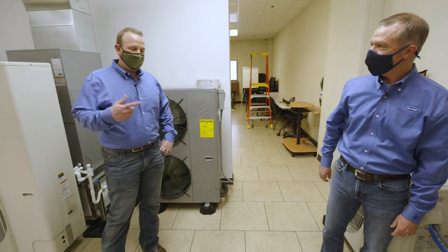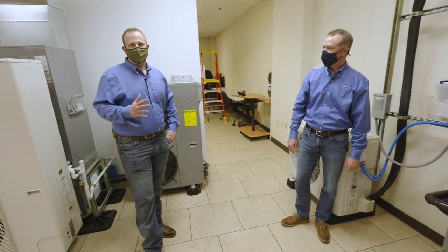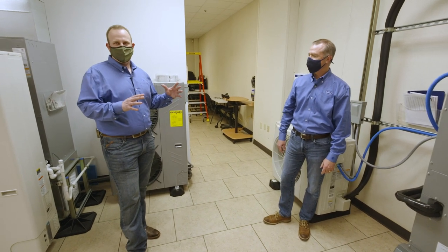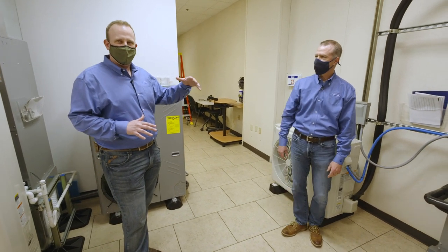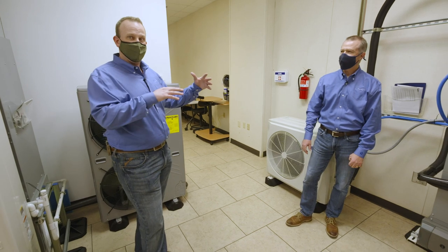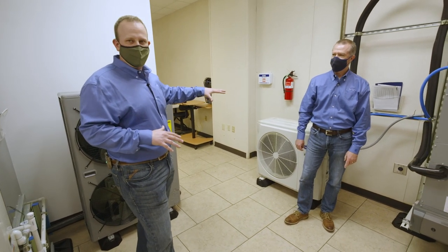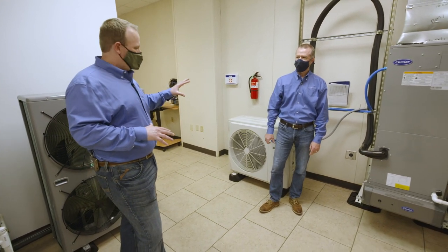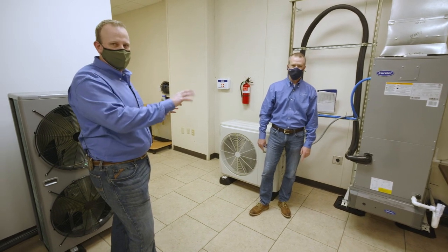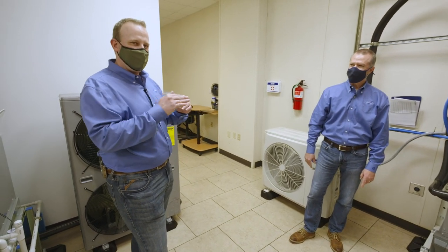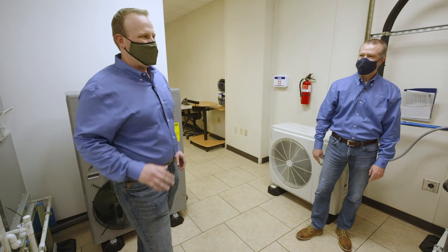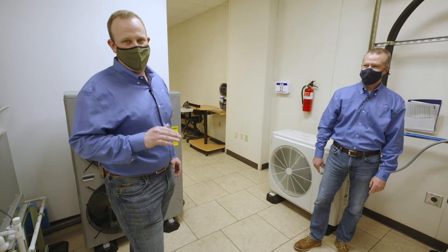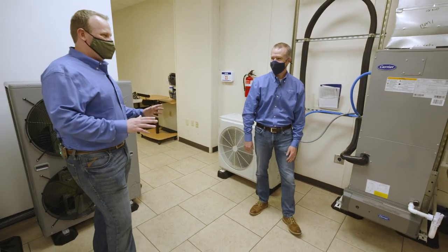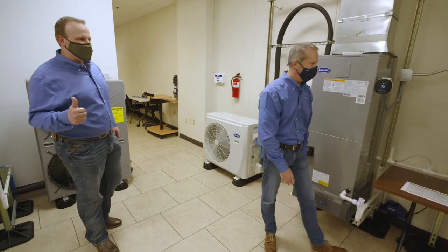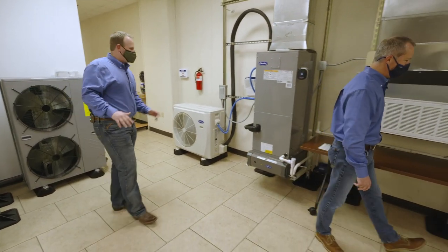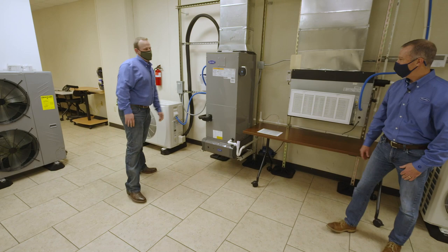Justin, you want to add anything to this? Yeah, one other thing to add about this system that's amazing. Normally with heat pumps, you start seeing the capacities fall off when you get around freezing or even before freezing. With this system, the 2-ton new performance outdoor unit paired with this, you almost have 100%, just slightly less than 100% capacity at -4 degrees outside while heating. That's amazing. So if you're on propane in the country or you don't have access to natural gas, think about what this will save you.